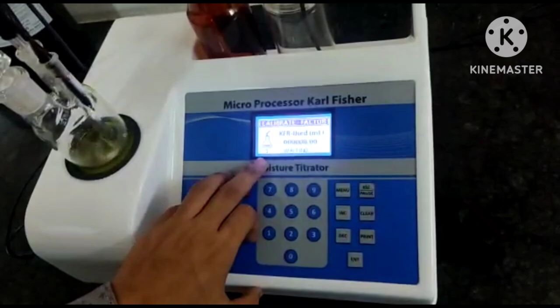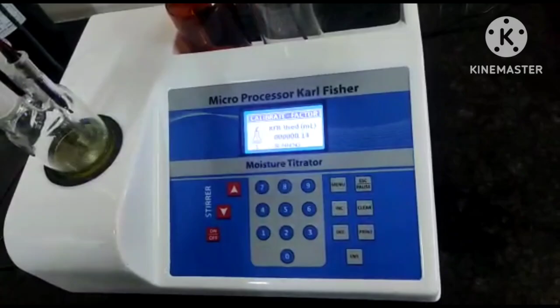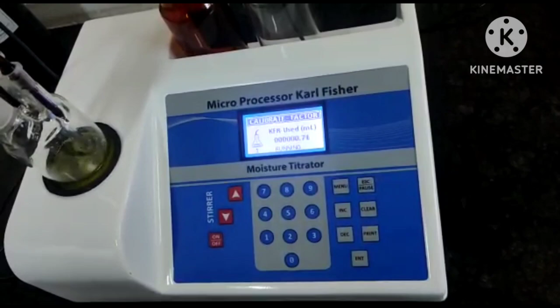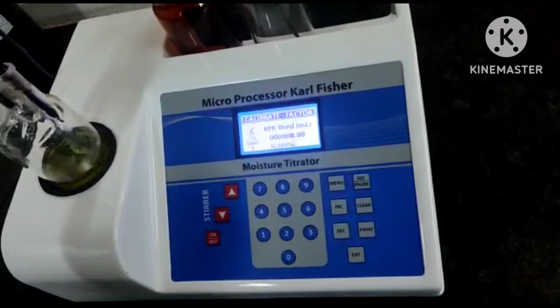A waiting signal is coming, so you have to wait. And this first option means you are doing this calibration first time. Suppose if you want to do this repeated time, 2 or 3 times, then after first reading you have to press increase button, and then you can repeat another distilled water calibration for taking the average value, the RSD value. So this is the first time, so we have to wait to get the neutralizing point, and then we will start with the next one.